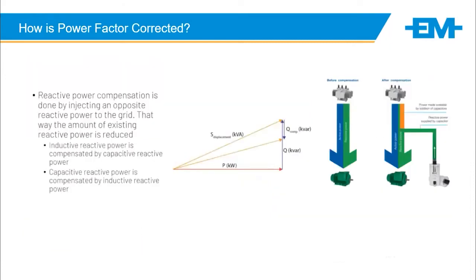So reactive power compensation is done by injecting opposite reactive power in the grid. I'm not going to jump into how the capacitor works and all that, but it creates a phase shift at the point of injection. And that is what brings down that demand at the point of injection. Okay. This is done by basically introducing capacitors into the network and bringing them in when it is required. Okay, so what we call this reactive power is now coming from the capacitor bank.